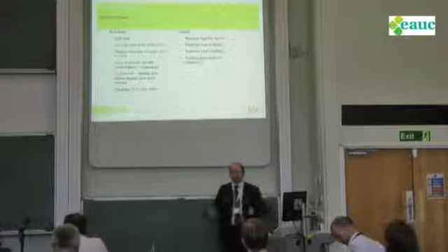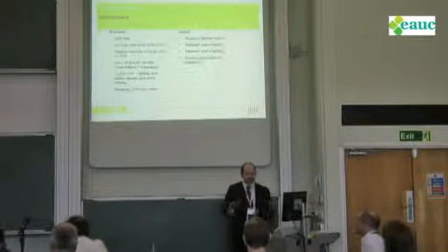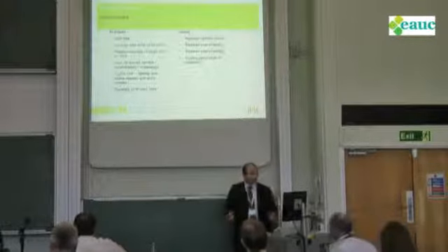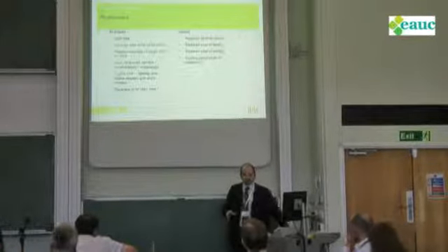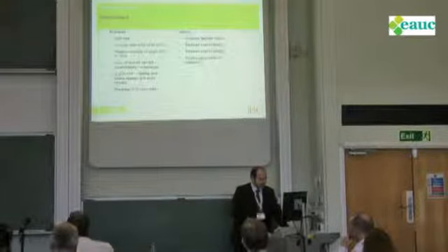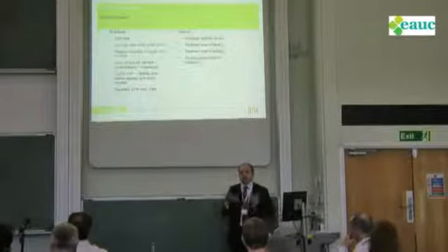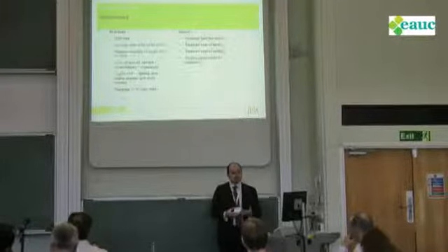So things like turning off unused servers, for the cost of a penny, saving you loads. Identify servers that aren't being used, turn them off. And if you can't find who uses them, turn them off and find out who shouts about it. Turn off your lights when you don't need them. Separate UPS plant area. UPSs have batteries. Batteries do not like to be warmed up.